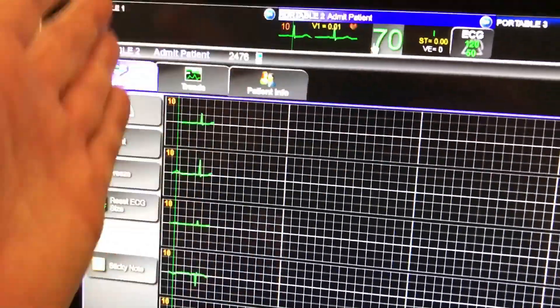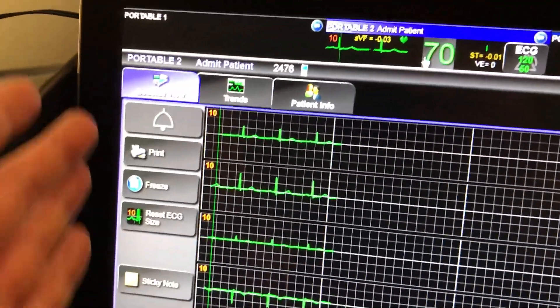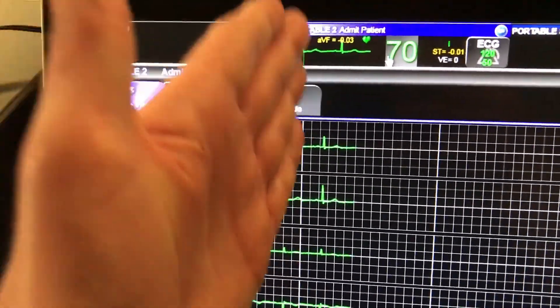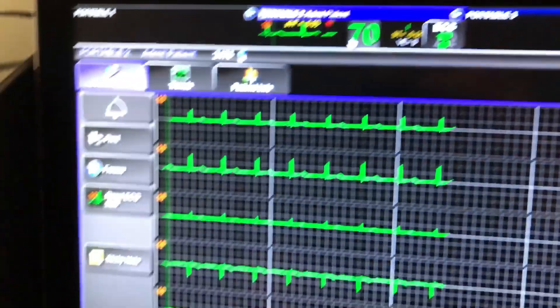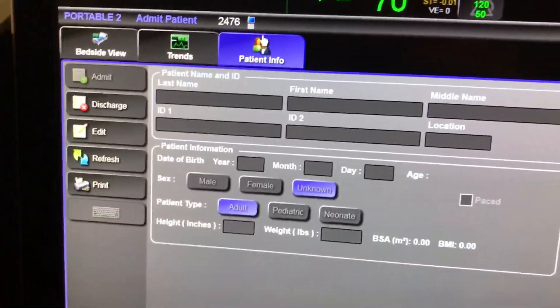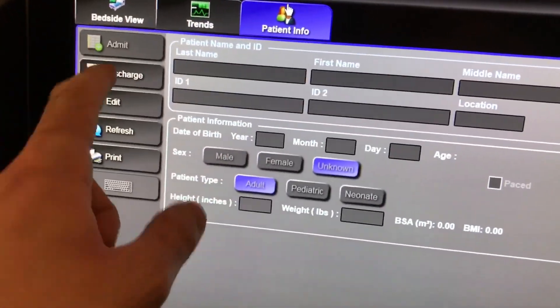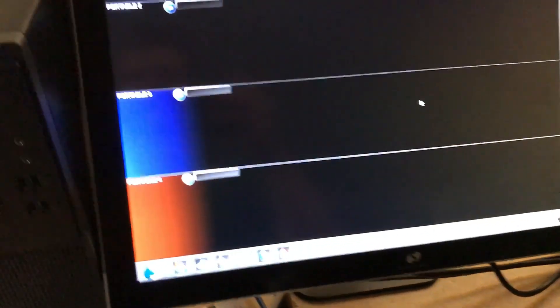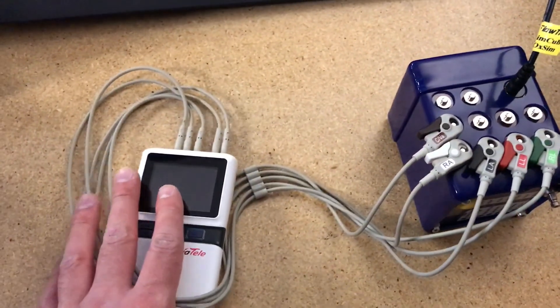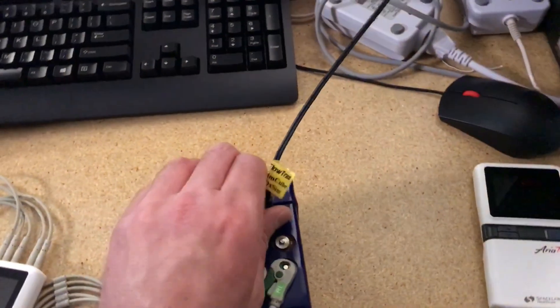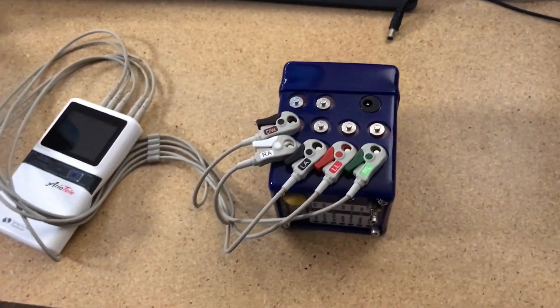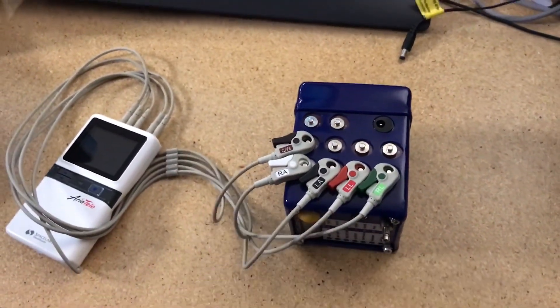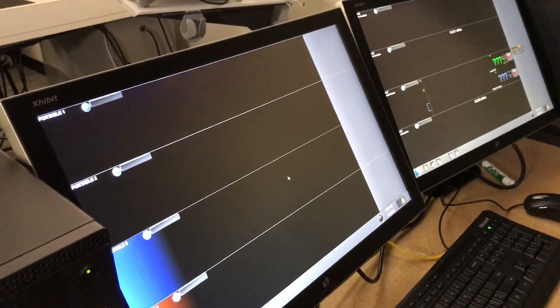So I just transferred it from portable one to portable two. So presumably, you could transfer them from portable to an actual bed unit. But in this case, what we want to do is just discharge the patient. Discharge. It will even, you couldn't really see it there, but it sent the detune requests. And now the portable unit is no longer tuned into the central station. So I can remove power from the simulator, and nothing's going to happen over there.